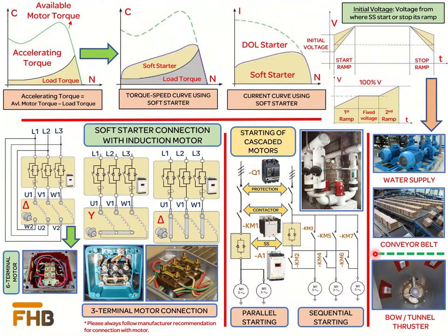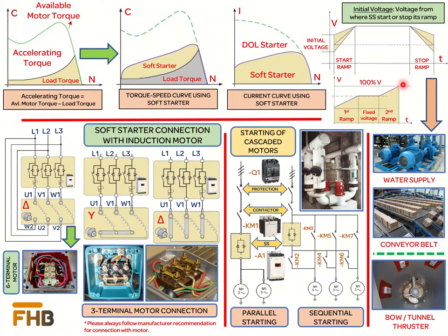Another technique is constant current starting. In this technique, the soft starter delivers voltage to the motor until it reaches the specified current level. At this specified current level, the voltage ramp is stopped until the current drops, and then the voltage ramp continues again towards the full voltage. Another technique is torque control, which provides constant acceleration torque during the motor startup by adjusting the motor power so that the motor accelerating torque remains as constant as possible.